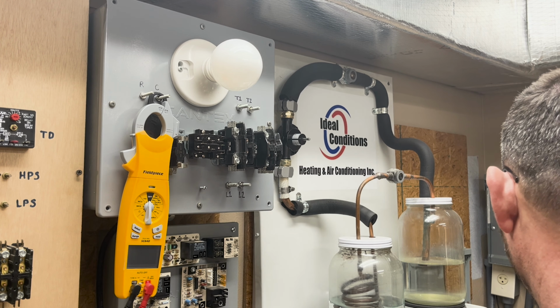A lot of people don't think about using a one-pole contactor. Remember I told you in the other videos, you only have to break one leg of power, whether it's for heat strips or motors, it doesn't matter. Your load can have the other leg present, because if the load requires the full 240 volts of electricity, then when it still has one leg of power, that's only 50%. That's not enough for it to energize, not unless it shorts the ground. It may run at half speed or something, which is not good, but which we could cover in other videos. I think a lot of people look at the one-pole contactor and don't really appreciate it to its full value.